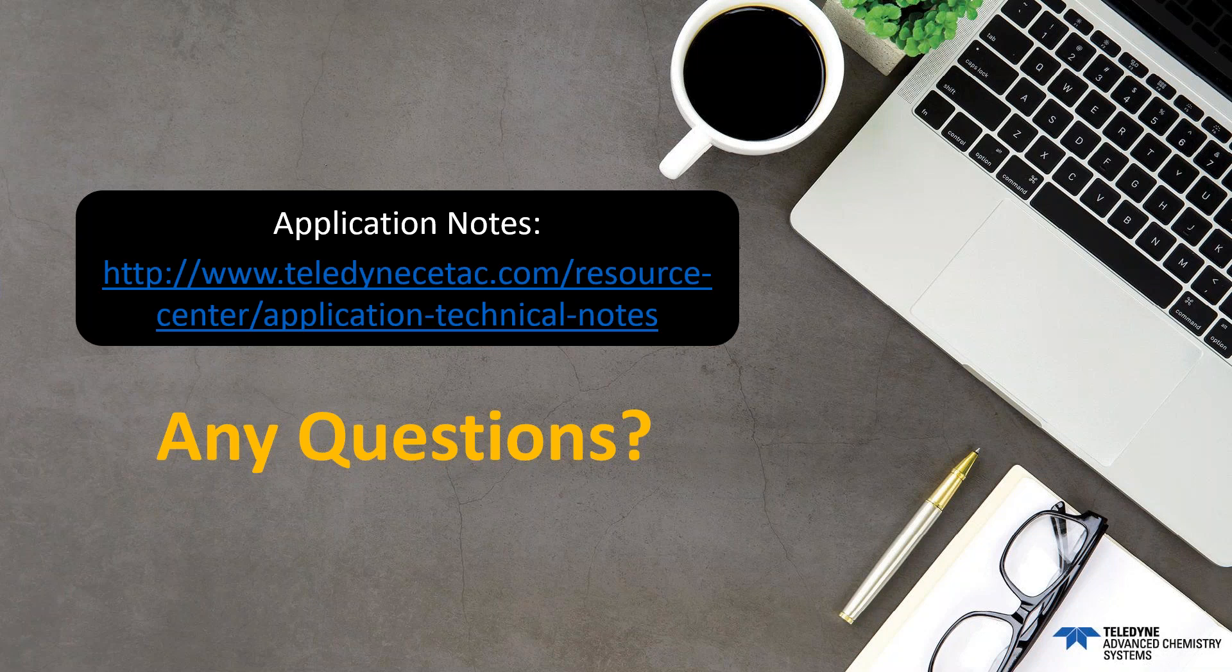All right. One thing that we did get in – will this work on my 520? And the AS Express Plus actually was introduced all the way back in 2011. So, it's a seasoned product that we have a lot of experience in different laboratories with. So, it does work on the previous iteration, the 500 series, 520s. It works on our current 560s, 280s. It also works on some other autosamplers like the Perkin Elmer S10 and a few others. And also, of course, in our Oils autosamplers like the ASX 1400 and the new Oils 7400 are all AS Express compatible.